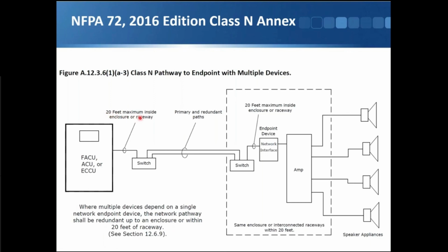is allowed between the panel and the first thing, because actually we've never required supervision. Well, not never. At some point in the past, it was put in there that it's allowable to go 20 feet of unsupervised wire in the same raceway or enclosure environment, and that was so that different modules and things could be interconnected. And some big systems have multiple cabinets, of course, and so you've got lots of reasons why you might want to allow 20 feet of wiring to exist without monitoring itself. So we said, okay, it's okay to not report a ground within this first chunk coming out of the panel.